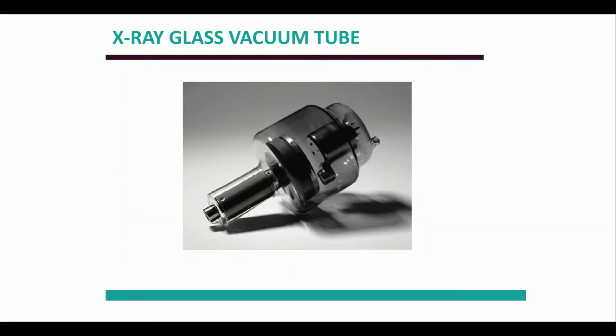The outer case of the X-ray head is made out of lead because lead is the type of metal that radiation cannot go through. Within that outer case, the tube head is made out of glass. The components inside are wrapped in glass, and it's a glass vacuum tube, meaning that all of the air has been sucked out of it in order to create the radiation on the inside.